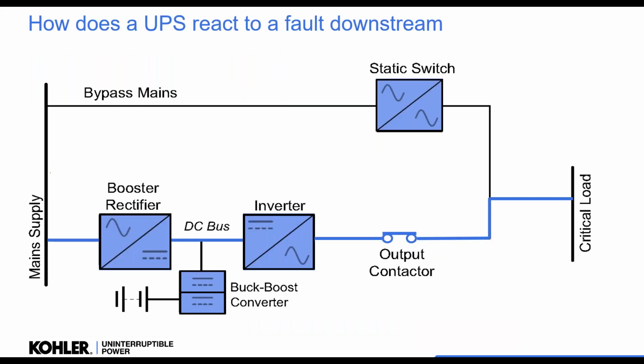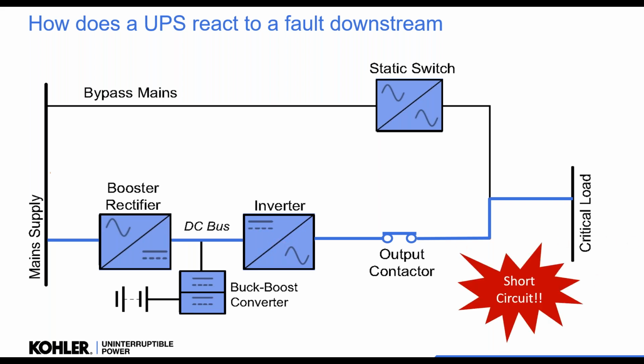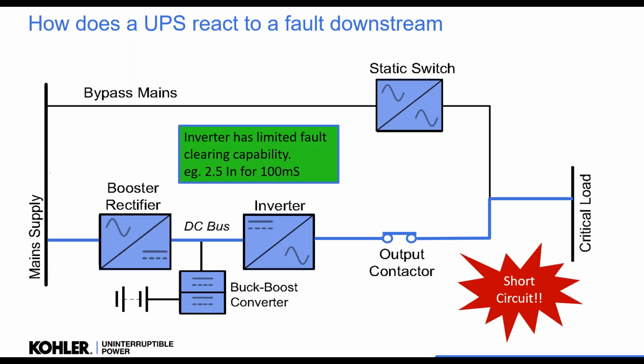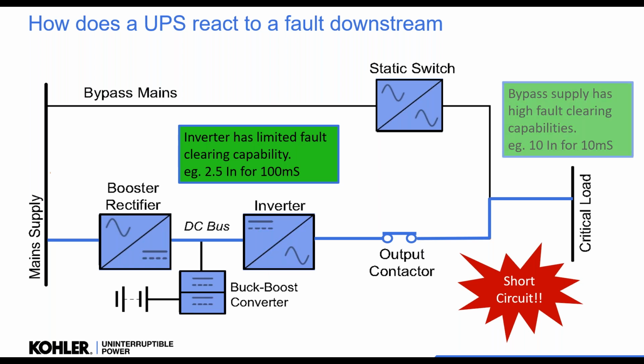So how does the UPS react to a downstream fault? The UPS is made up of mains to the booster rectifier, inverter feeding the critical load. So if we have a short circuit on the output, we have limited fault capability on the UPS. The inverter is an electronic device. We've got limited fault current, maybe 2 to 3 times the nominal current for maybe 40 to 200 milliseconds. The bypass supply, if available, is mains and has much higher capability, maybe 10 times the nominal current for 10, 20 milliseconds.